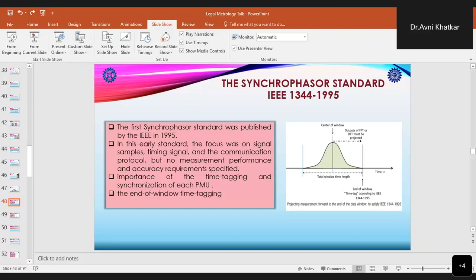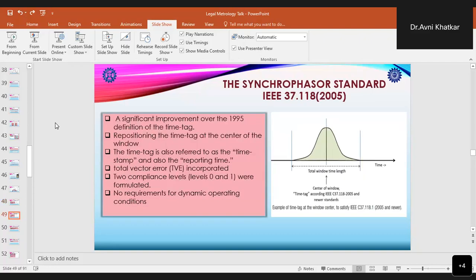So for improvement, this standard was revised, and a significant improvement was seen over the 1995 standard in the 2005 standard, basically on the basis of the redefinition of the time tag. Repositioning the time tag at the center of the window was done, which removes the need to project the measurement forward in time with all the uncertainty that brings. Window center time tag placement continues to be the most modern version of the standard. This center of the window time tag is now referred to as the timestamp and also the reporting time.